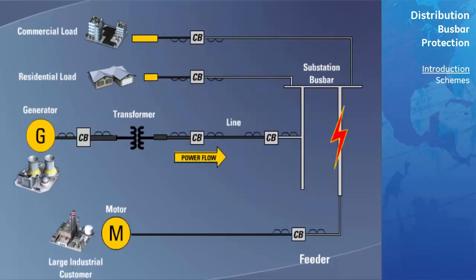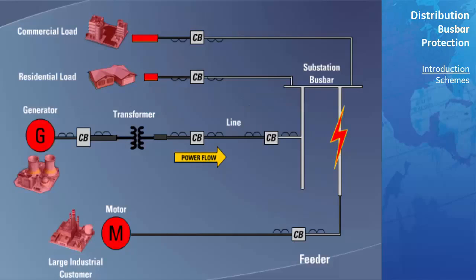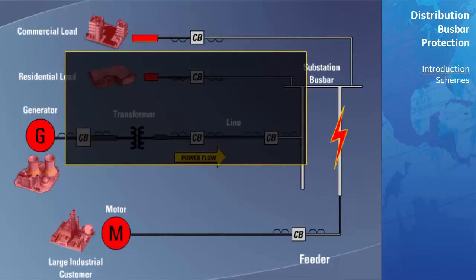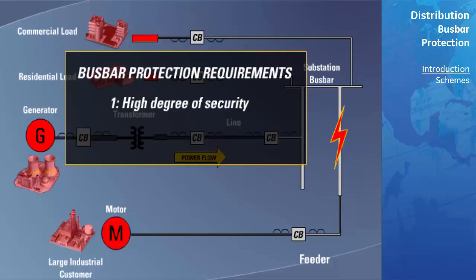A false trip of a distribution bus can cause outages to a large number of customers, as numerous feeders as well as sub-transmission lines may be disconnected. A false trip of a transmission bus bar may drastically change system topology and jeopardize power system stability. Hence, one of the requirements of bus bar protection is a high degree of security. On the other hand, bus faults generate large fault currents. If not cleared promptly, they endanger the entire substation due to both dynamic forces and thermal effects. As a result, the second requirement of bus protection is that of high speed operation. With both security and dependability being very important for bus bar protection, the preference is always given to security.